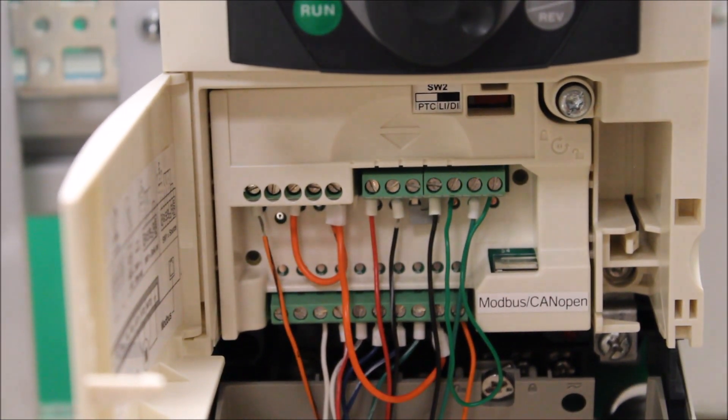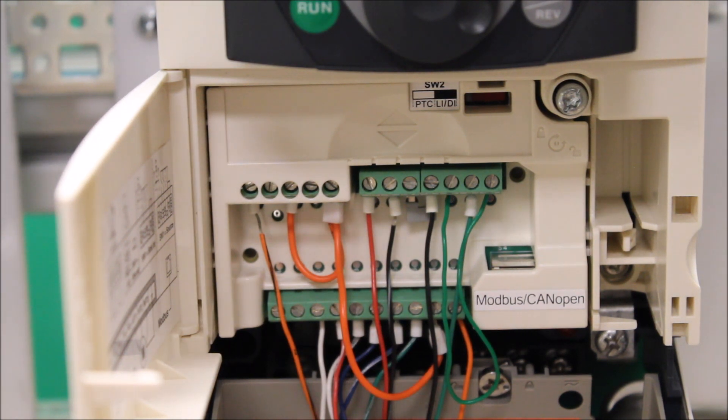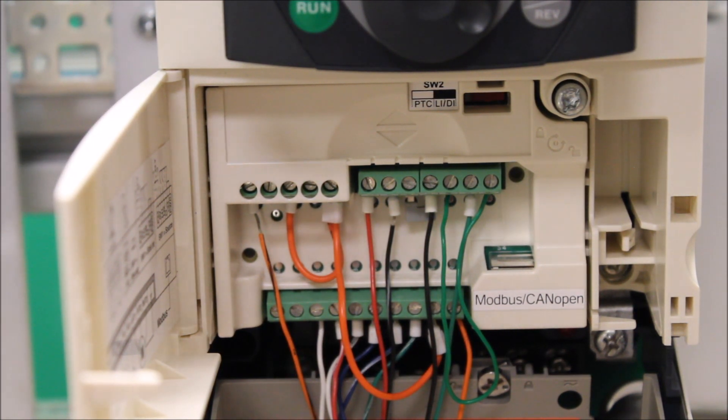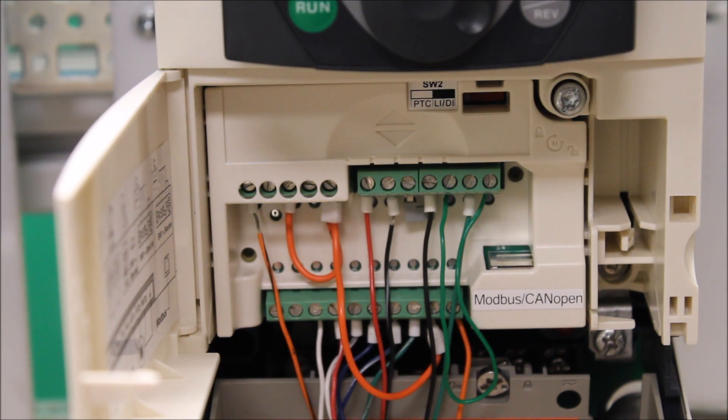Just to give you a background here, source mode is the default setting and that's basically where the drive is getting toggled in the logic input side of things with the 24 volt supply toggling it on and off.